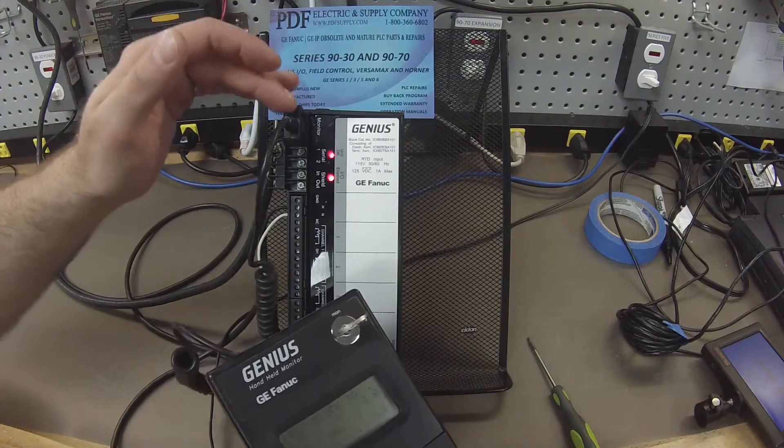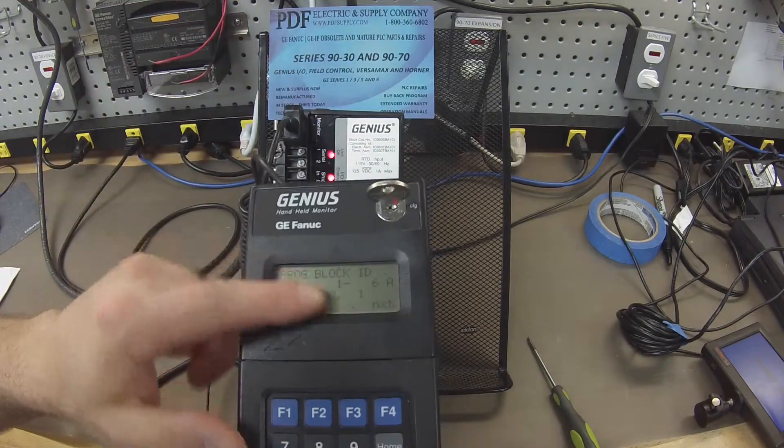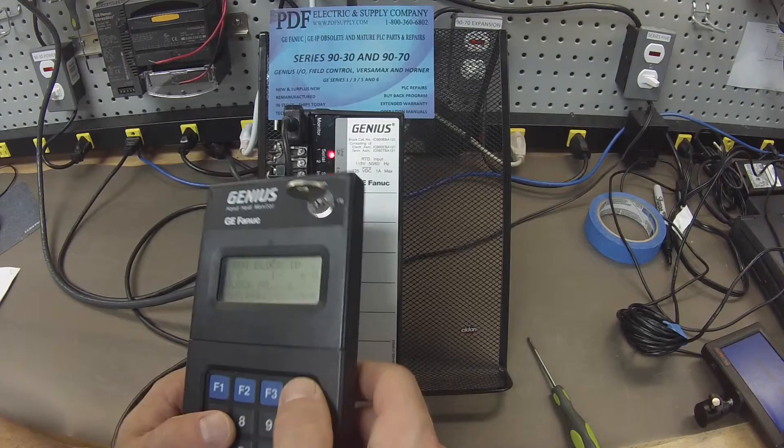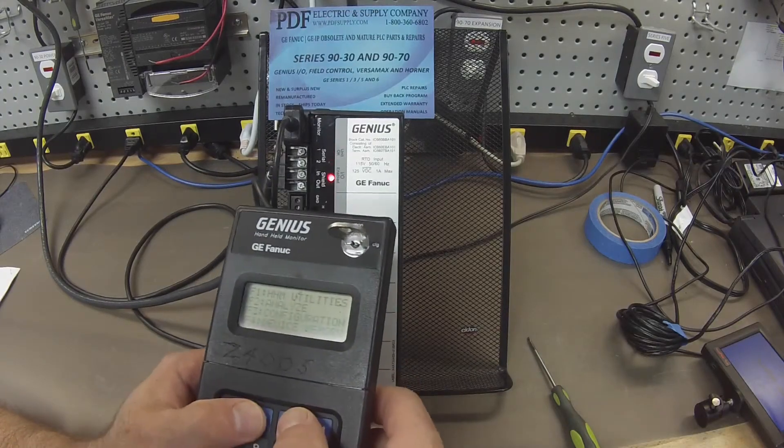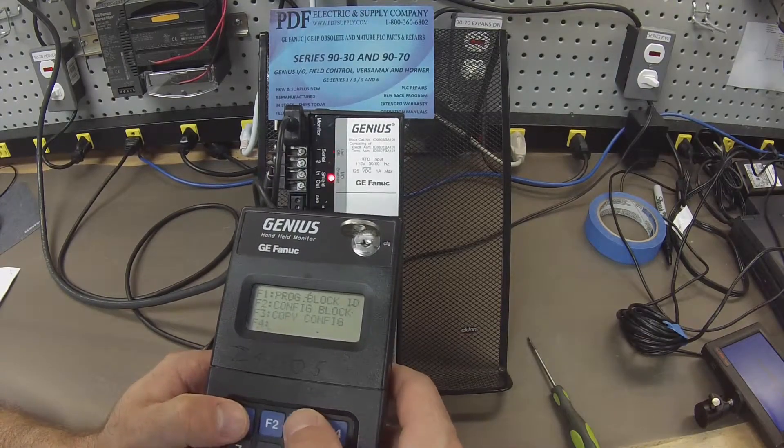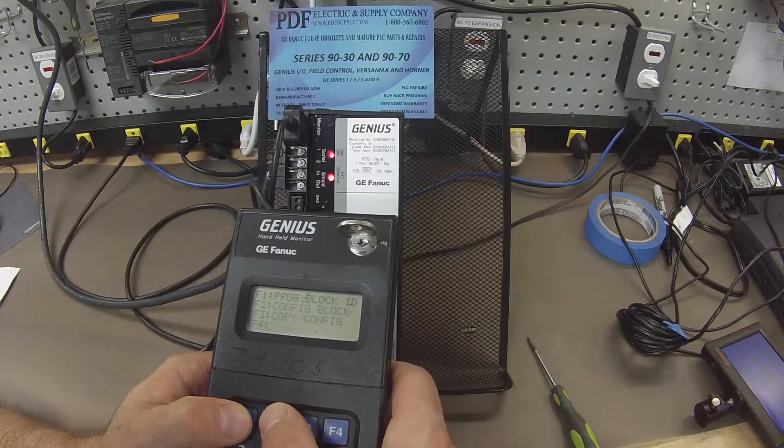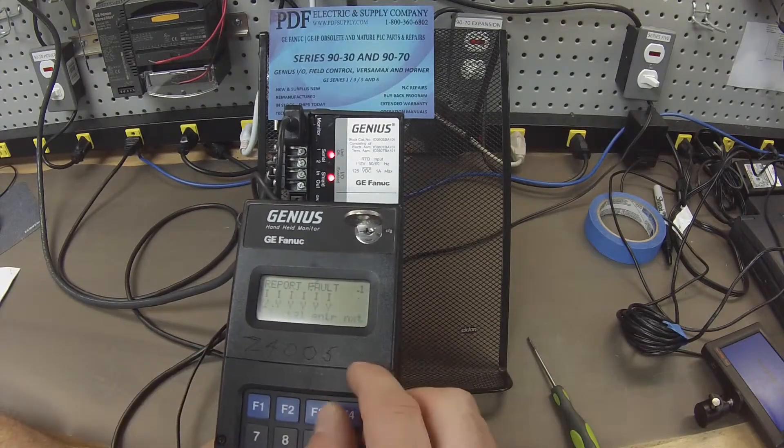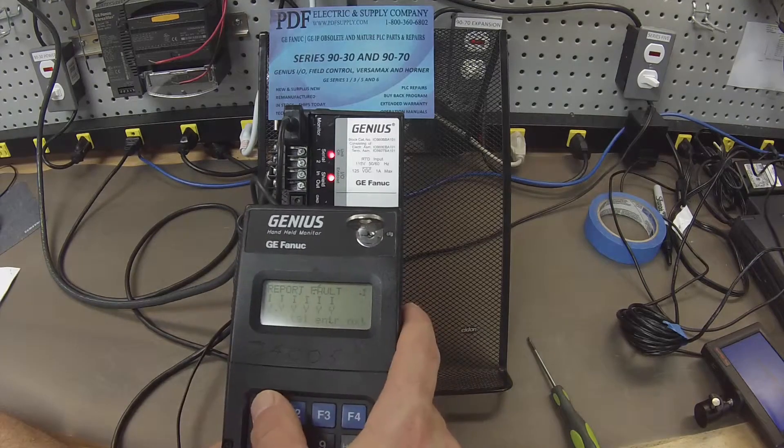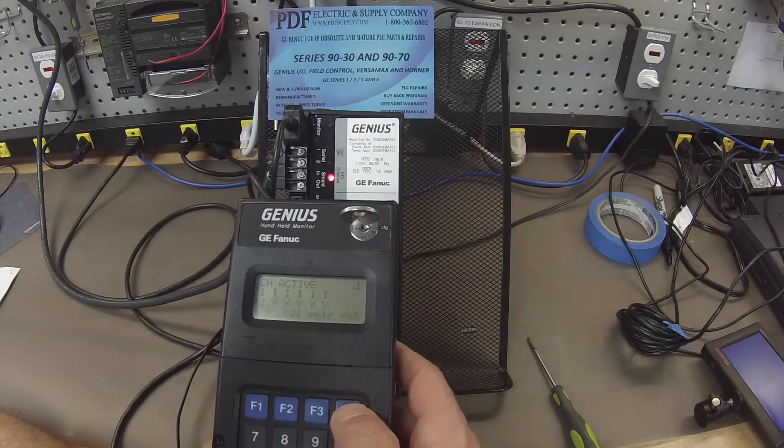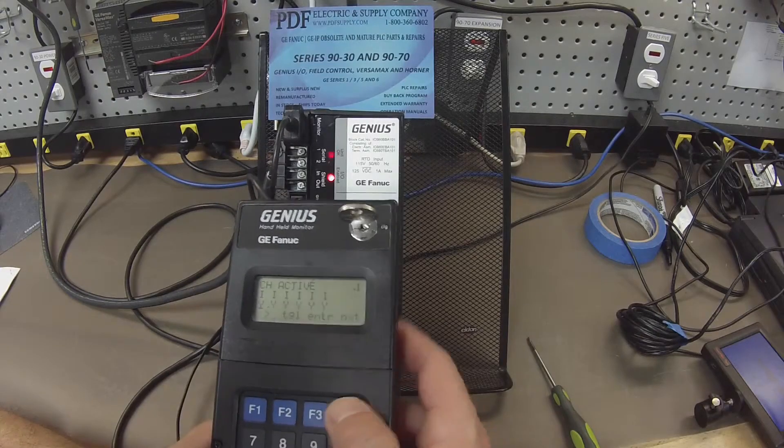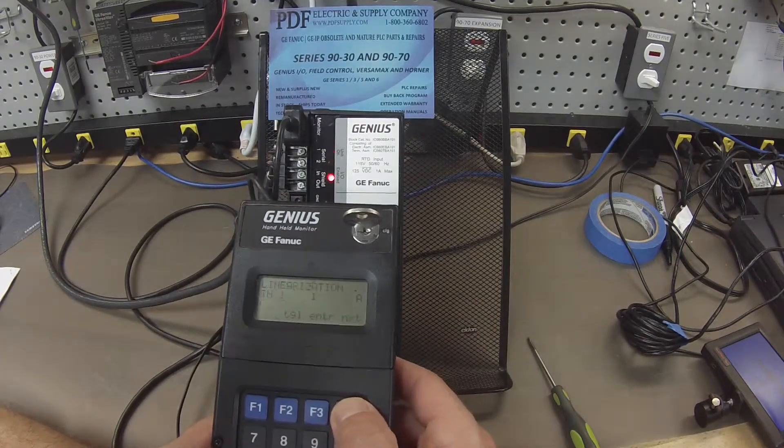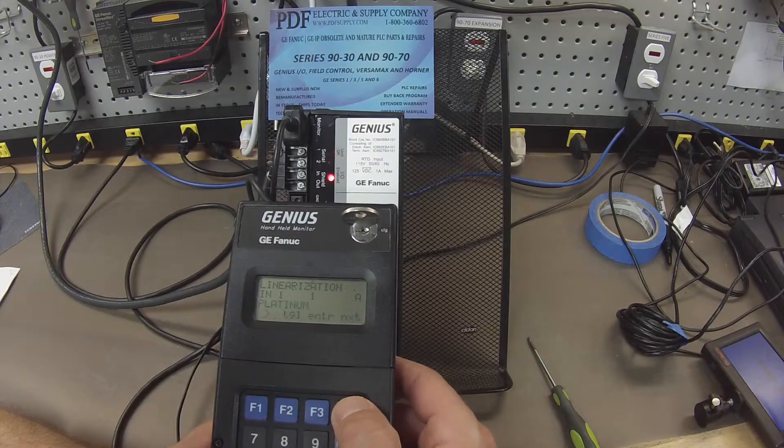We know that the monitor is working because I've been able to program it. So the next thing I want to do is check my configuration. So it's F3, F2. I do want to report faults yes for my purpose. I do want all channels active. I'm going to have them selected as yes. And the rest of these settings are the factory settings.